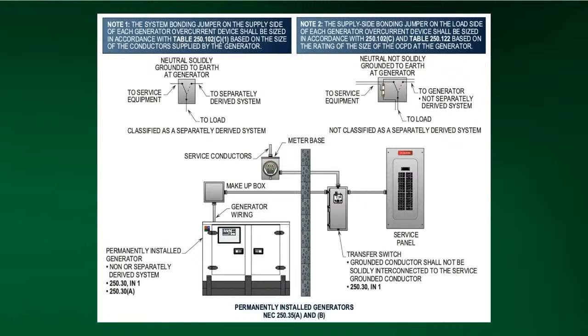Sure. Now, what we did here, we have two different illustrations, and it depends on if it's considered a separately derived system or non-separately derived system. So the second one, you'll see where we're coming in and we look at 250.35 A and B, and this is where we talk about permanently installed generators. But the point I'm going to point out here is right up above the main portion of the illustration. You're going to see we show two different types of terminations within the automatic transfer switch, and whether or not it's classified as separately derived or not. And what we're telling you here is, if you switch the neutral, it's separately derived. If you're not switching the neutral, then it's not considered a separately derived system. Now, those are the 2 points I just wanted to point out.